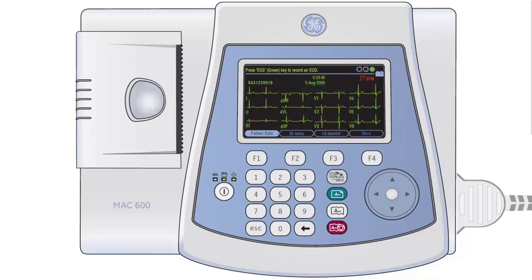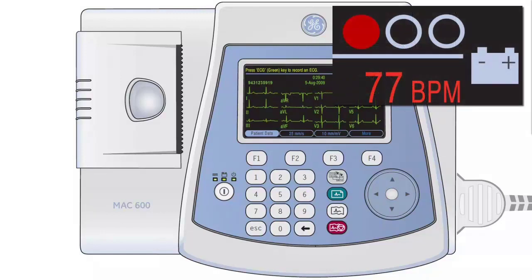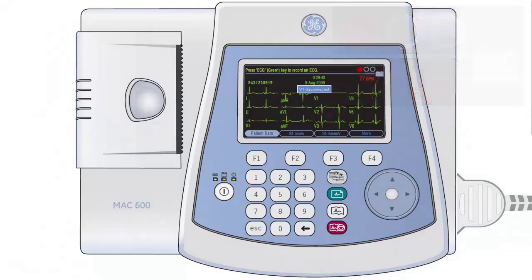A red indicator means that one or more of the leads has a very poor connection or has become completely disconnected. The machine will attempt to identify and indicate the problematic lead. If the machine does not indicate the exact lead with the problem, all leads should be checked for good, secure connection to the patient.